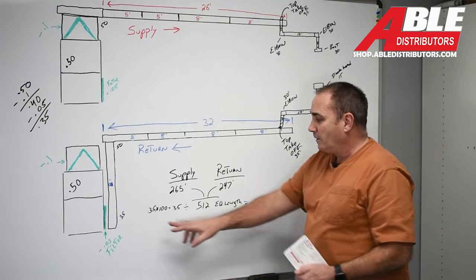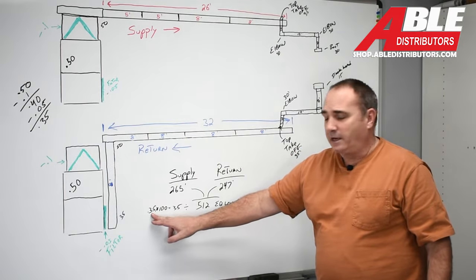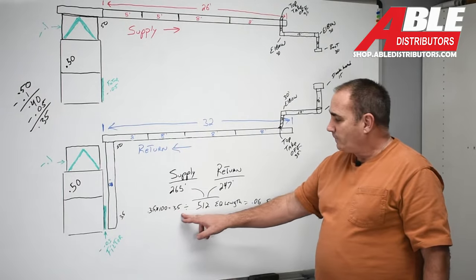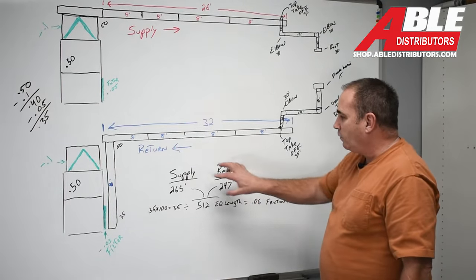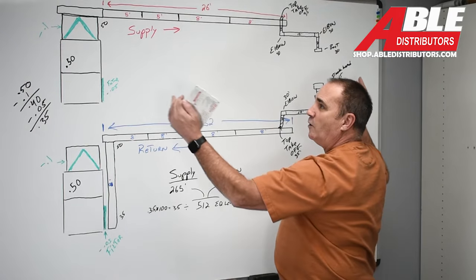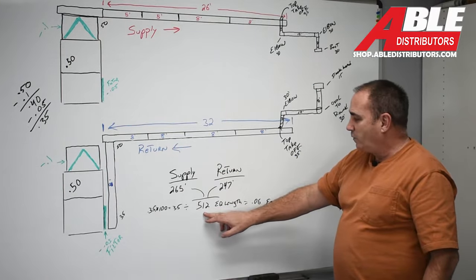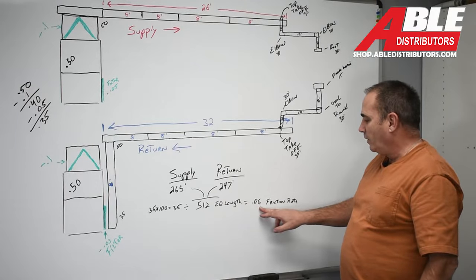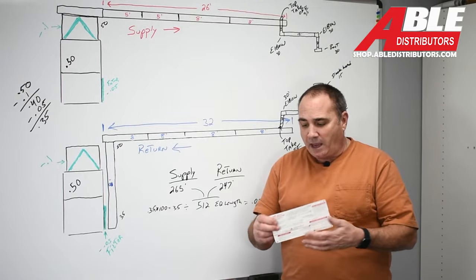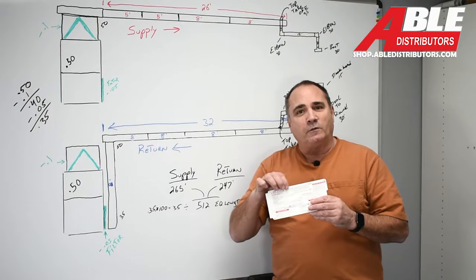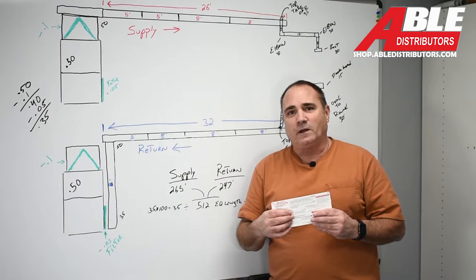Now we take that 0.35 of available static, multiply it by 100, gives us 35. Divide that by the total equivalent length of the longest return length and the longest supply length. That's 512. We do the math, gives us 0.06. So now we have what this system we need to calculate and the friction rate we're going to use when we're calculating CFMs.